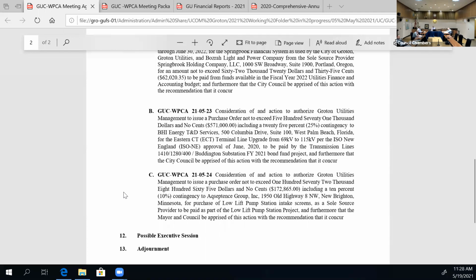So we're going to be converting the 69,000 volt substation terminal, which is bus 1, to 115 kV. And the timeline for that, we need to complete it by June 2023 in order to meet the ISO deadline, which they've given us a 3-year window for. So this gives us a jump.